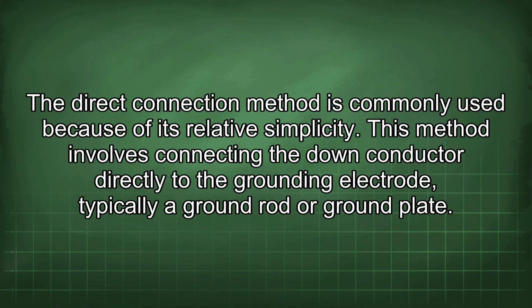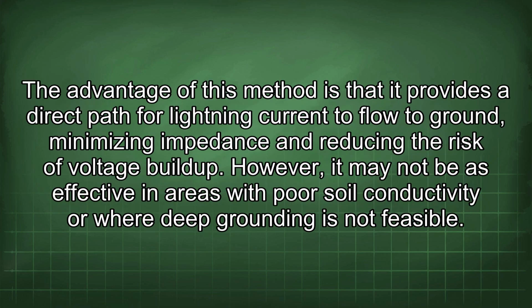The direct connection method is commonly used because of its relative simplicity. This method involves connecting the down conductor directly to the grounding electrode, typically a ground rod or ground plate. The advantage of this method is that it provides a direct path for lightning current to flow to ground, minimizing impedance and reducing the risk of voltage buildup. However, it may not be as effective in areas with poor soil conductivity or where deep grounding is not feasible.